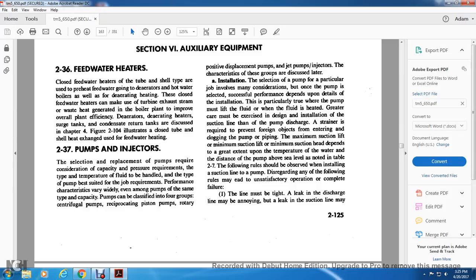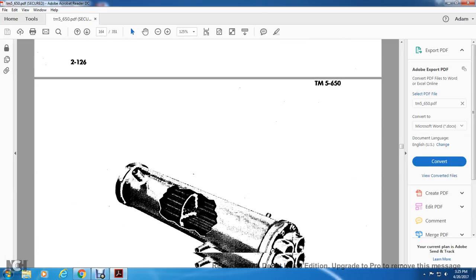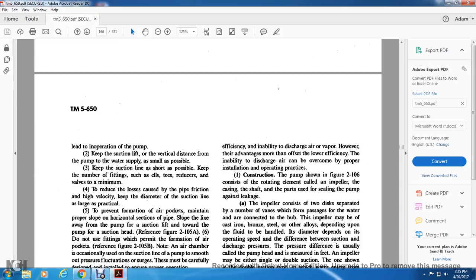The following rules shall be observed when installing a pump suction line. Disregarding any of the following rules may lead to unsatisfactory operation or complete failure. One, the line must be airtight. A leak in the discharge line may be annoying, but a leak in the suction line may lead to interruption in operation of the pump.